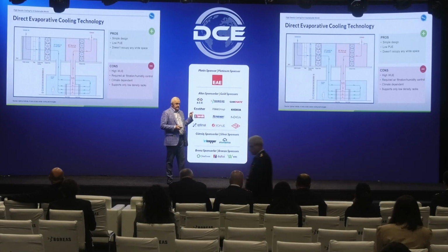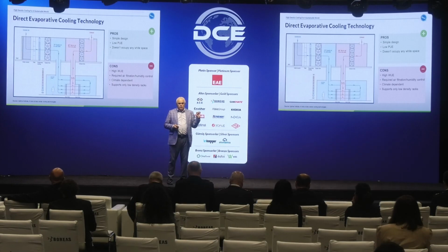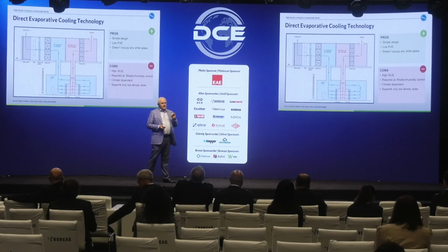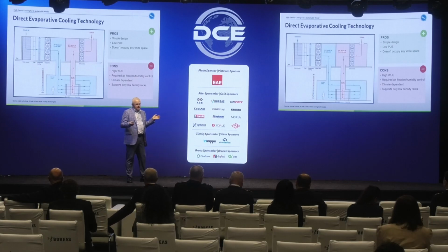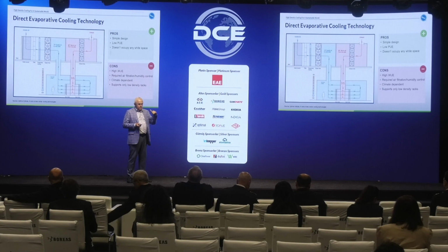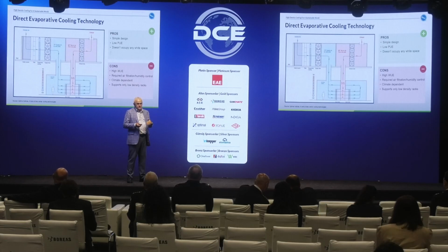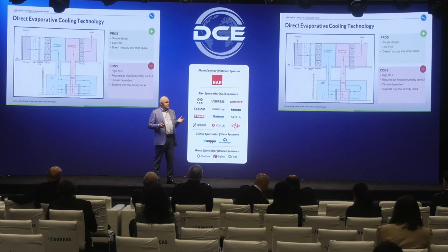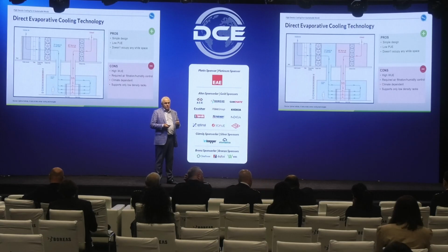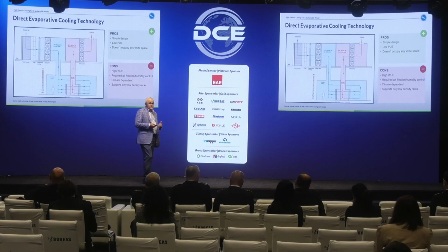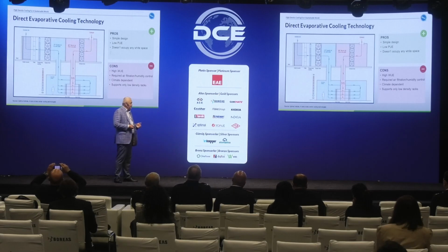But the problem with direct evaporative cooling is that you cannot control the humidity. On a very humid day out there, you bring the humidity inside. Despite the fact that the new standard is between 8 and 80%, you are still at the mercy of the weather. And the second thing, you must filter the air. If we discuss a large data center, I've seen data centers the size of this entire exhibition center, talking about 1.5 million CFM. Imagine how to filter 1.5 million CFM, and how much you have to spend on those filters.